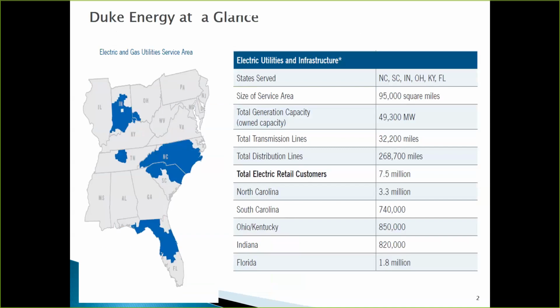So a little bit about Duke Energy. For those of you that are probably in our service area, we're a large utility. We have a presence in 6 states now, several million customers. And we have in service just in this area, in the upper portion of North Carolina and South Carolina, 3,000 of these devices. We use these things for metering, for protection, for control. So they're a very prevalent device, and it's a very cheap, economical way to step down your nominal transmission voltages, 100 kV, 230 kV, down to a usable value. And that's why we use them.